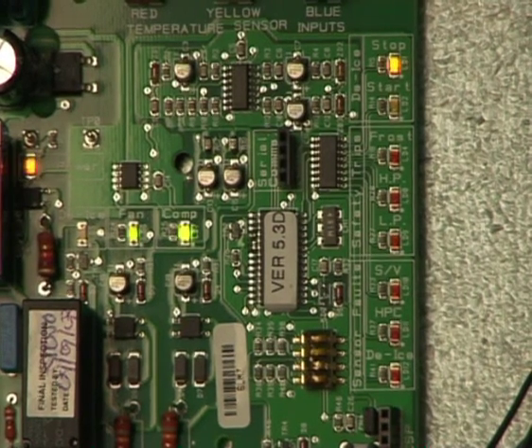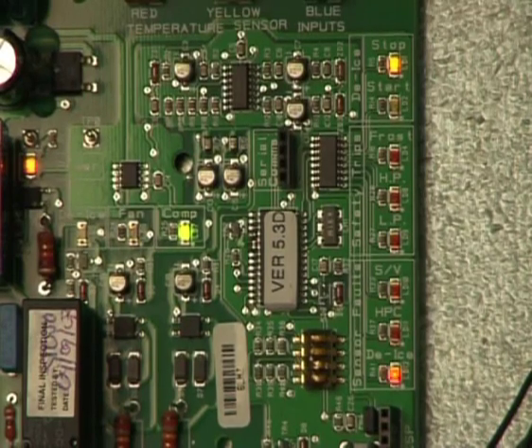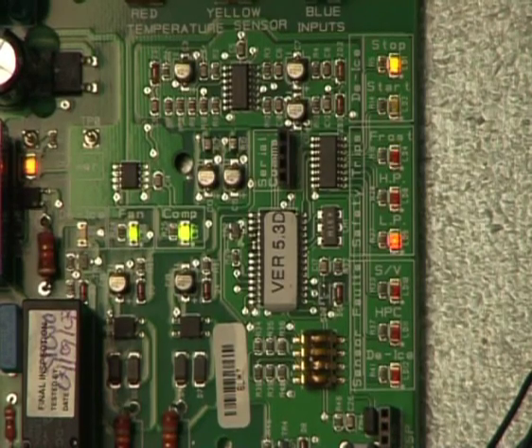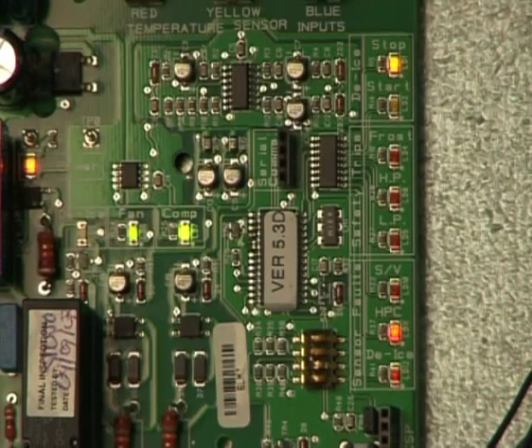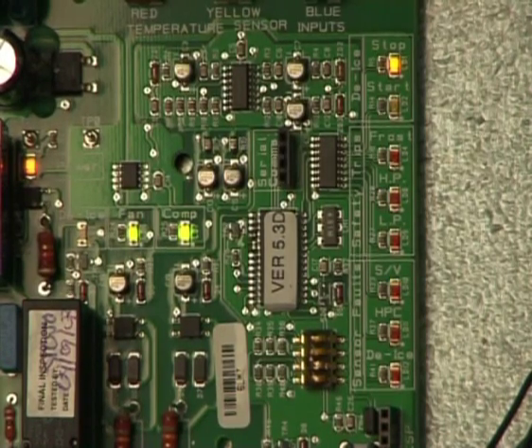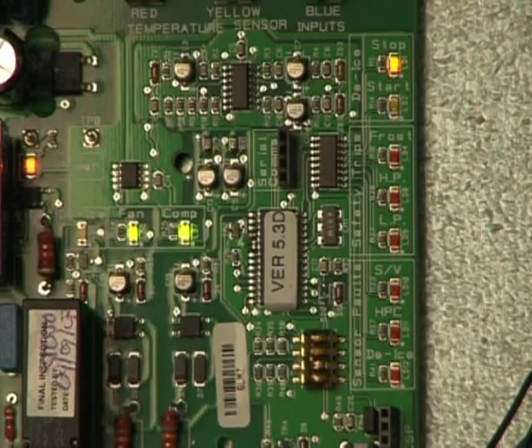There are 2 built-in safety timers associated with the compressor, a minimum compressor run timer which is designed to ensure the compressor runs for a minimum of 90 seconds. This ensures oil return to the compressor. If the compressor signal is removed from the compressor terminal in under 90 seconds, the column of LEDs will flash from top to bottom to advise minimum run timer has been activated. This timer is not adjustable.